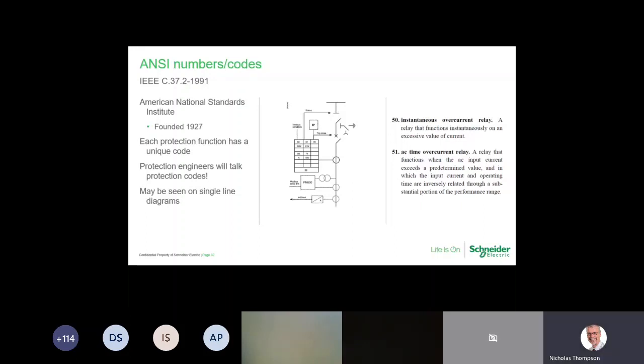And I've put up two there, 50 and 51. So these are for overcurrent protection. So 50, it's using the instantaneous protection curve, and for 51, you're using a time delay curve. And there are other numbers for other protection functionality, and our protection relays can have a number of these already pre-programmed into them. And it's a case of when you're setting up the relay using the software, you can select the different ANSI protection codes to do whatever you want it to do.